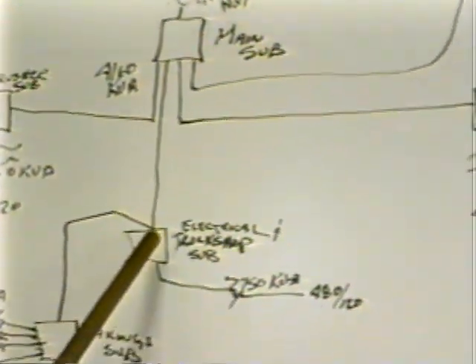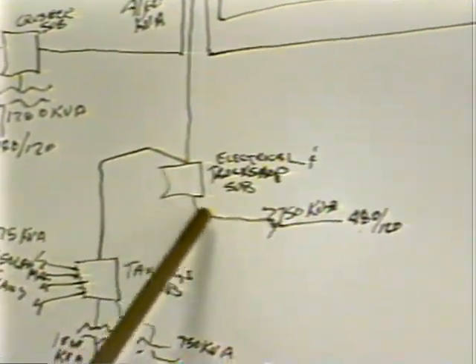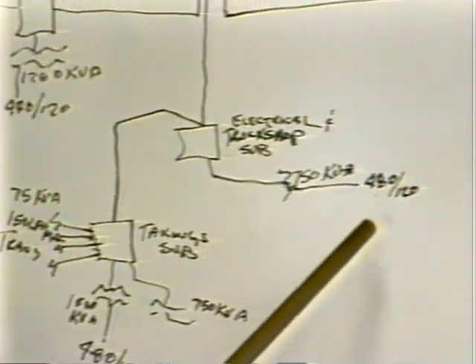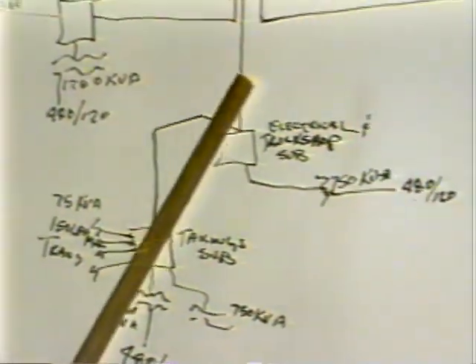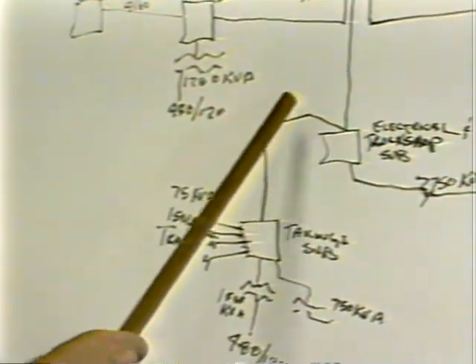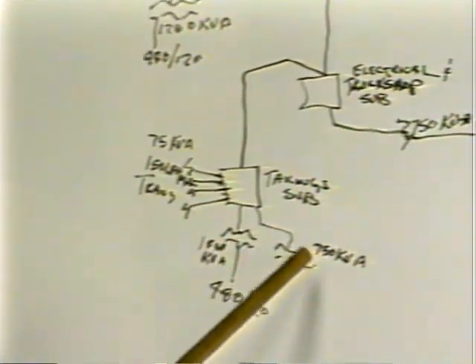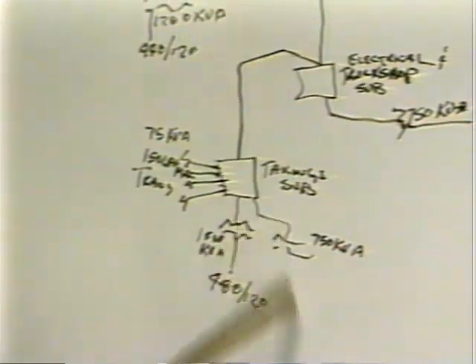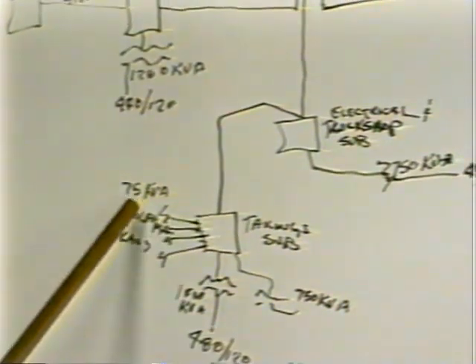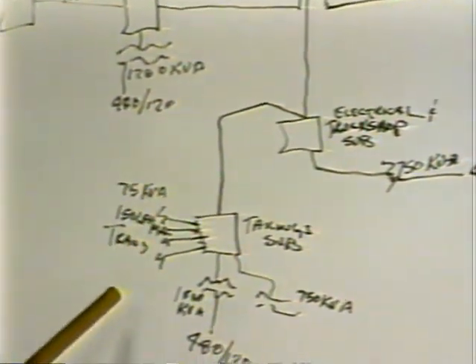Another feeder that comes from the main sub feeds into the electrical and truck shop. That is fed from a 750 kVA transformer, and that is distributed down to our 480 and 120 volt areas. From the truck shop substation, its paralleled feeder is 4160 also to the tailing sub. Tailing sub then has 2 transformers. One is a 750 kVA, the other one is 1000 kVA. That distributes down to our 480 volt feeders also. Also coming out of the tailing sub, we have 4 75 kVA transformers. They're isolation transformers that feed our Reliance variable speed drives.